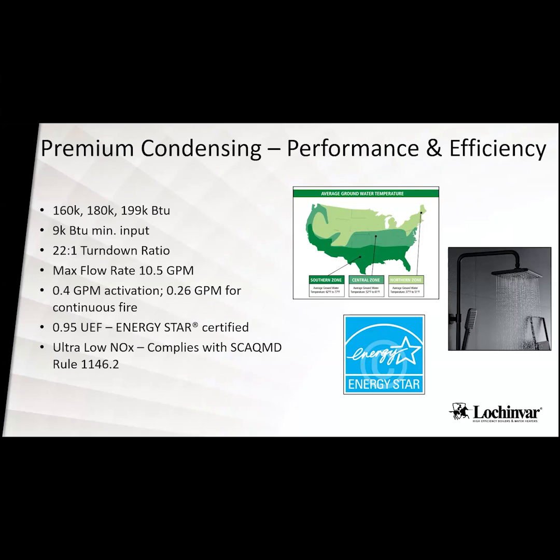The max flow rate of this unit is 10.5 gallons per minute. At a 70-degree rise, it's 5.8 gallons per minute. That's kind of industry standard around the board with all the other manufacturers. That flow rate matches exactly what their flow rates are through their units. For activation for this unit, it's 0.4 gallons per minute. But once it is activated, it can modulate down to 0.26 gallons per minute.